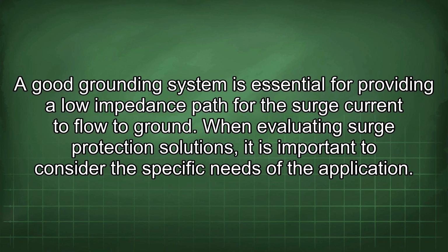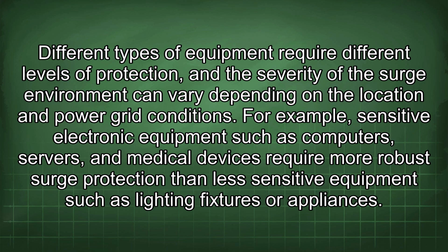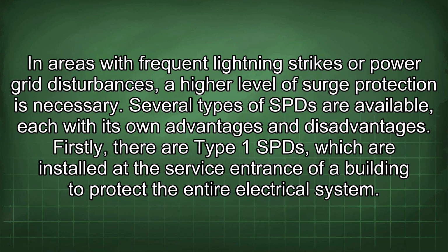When evaluating surge protection solutions, it is important to consider the specific needs of the application. Different types of equipment require different levels of protection, and the severity of the surge environment can vary depending on the location and power grid conditions. For example, sensitive electronic equipment such as computers, servers, and medical devices require more robust surge protection than less sensitive equipment such as lighting fixtures or appliances. In areas with frequent lightning strikes or power grid disturbances, a higher level of surge protection is necessary.